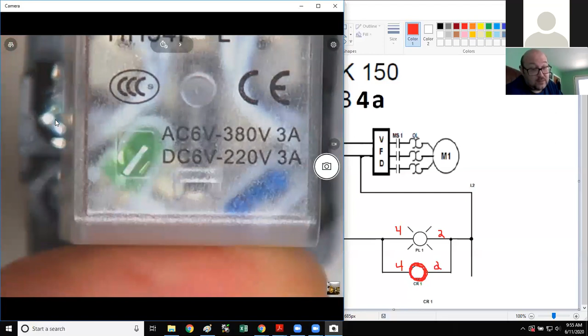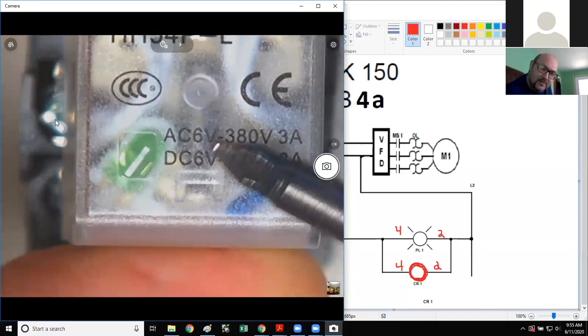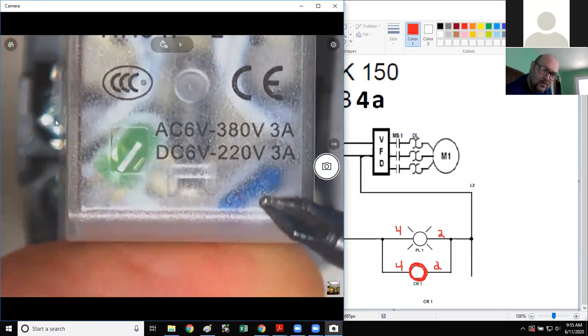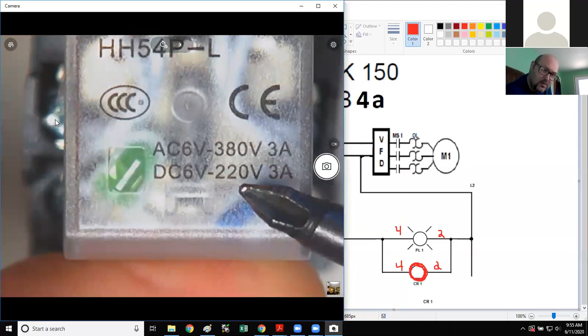This is 24 volts. Every ice cube relay is going to have some different ratings on it. This one is rated so the coil will operate anywhere from AC 6 volts to 380 volts, or DC 6 to 220. So we're well within that range when we're using DC 24 volts.